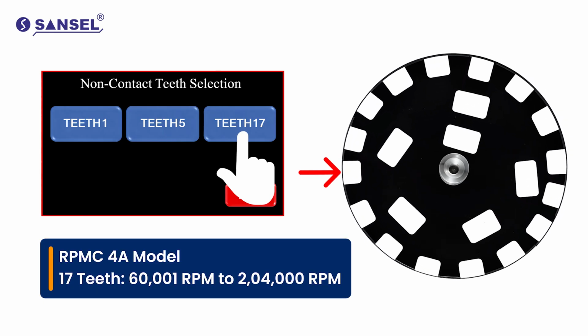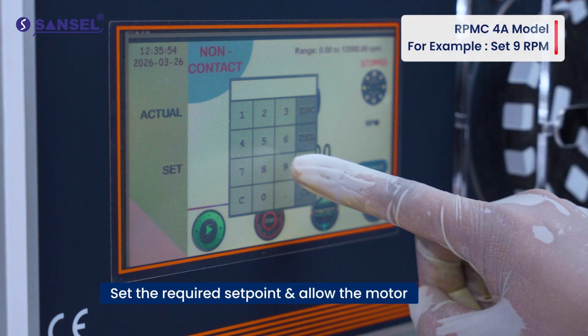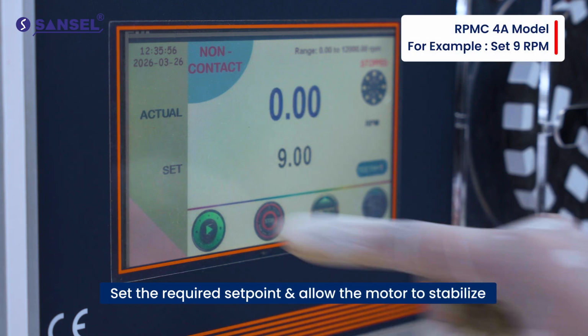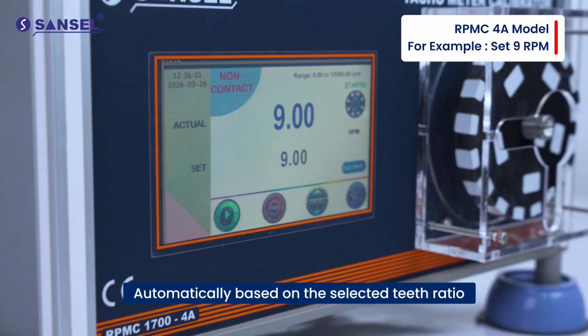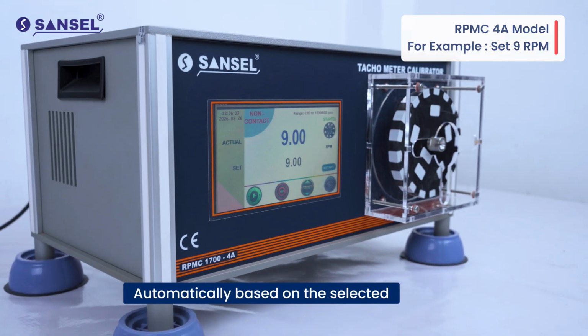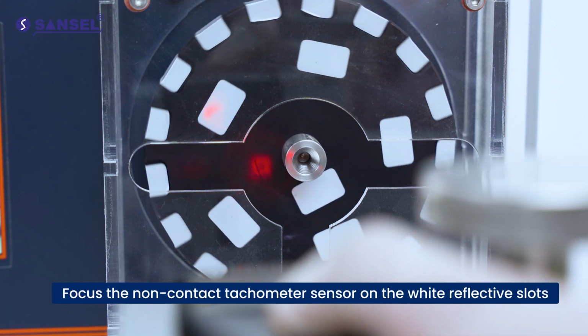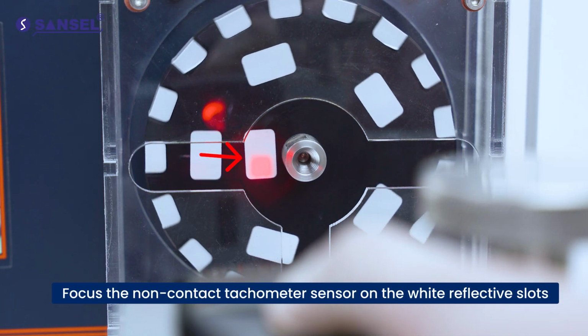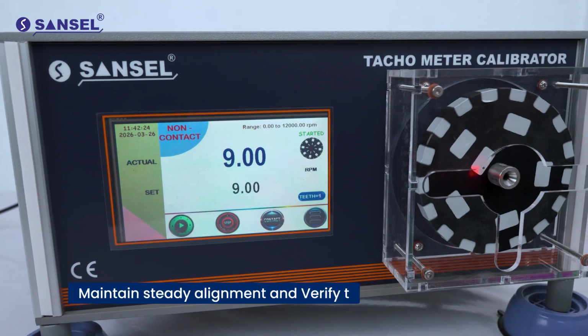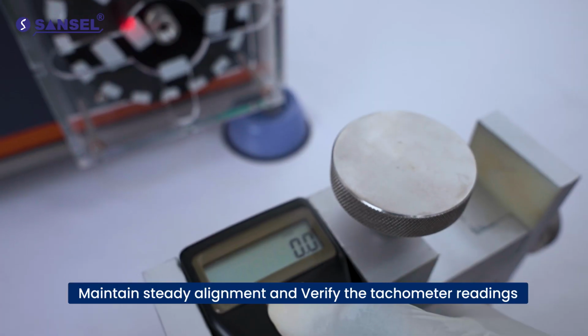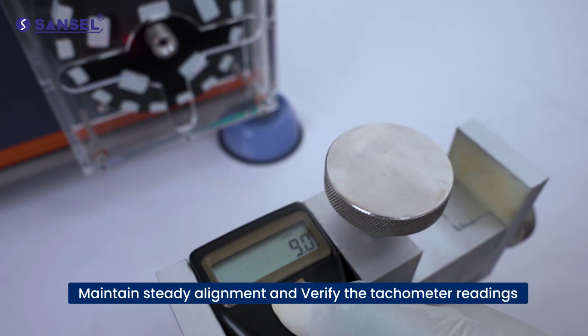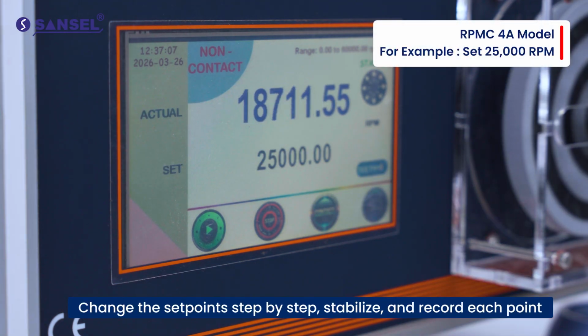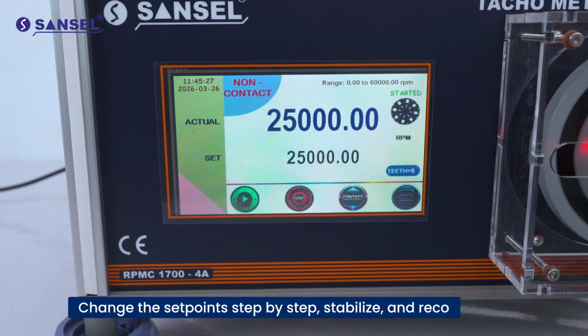to 2,04,000 RPM. Set the required set point and allow the motor to stabilize automatically based on the selected teeth ratio. Focus the non-contact tachometer sensor on the white reflective slots, maintain steady alignment, and verify the tachometer readings. Change the set points step by step, stabilize, and record each point.